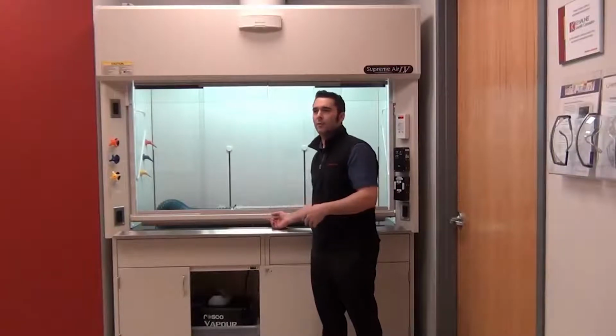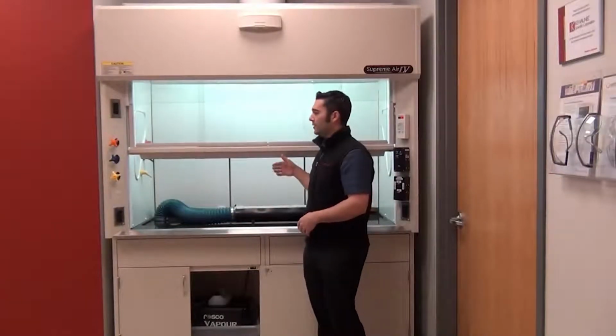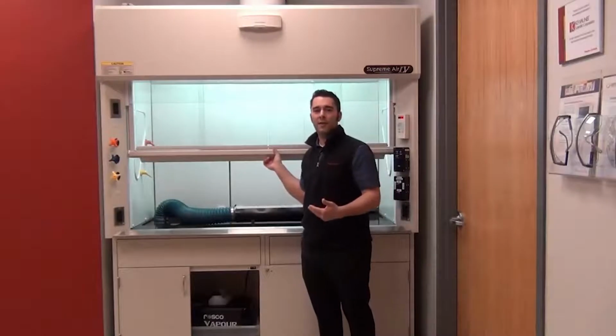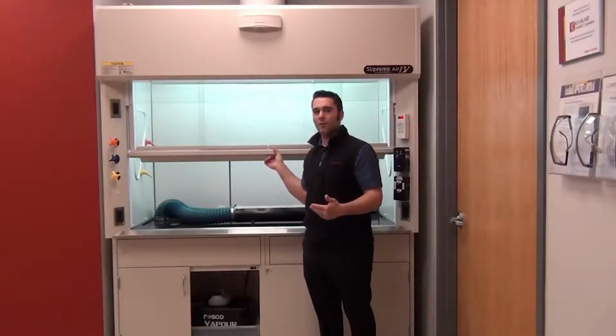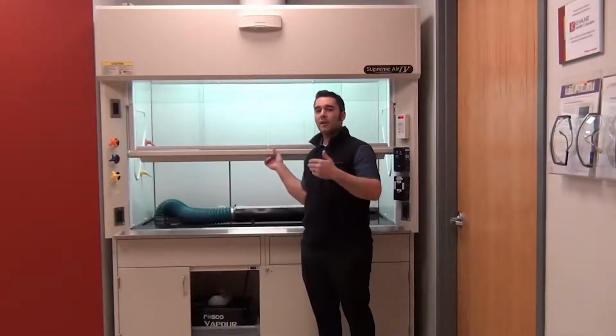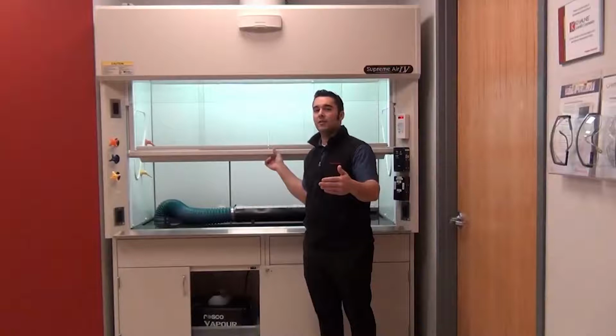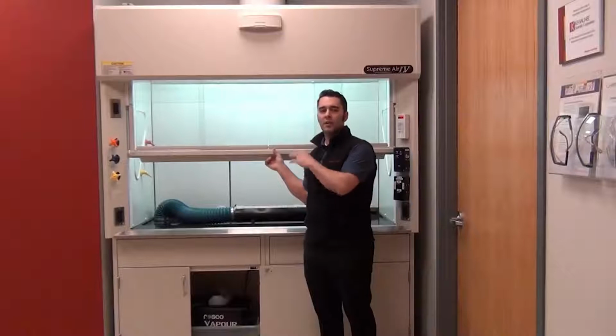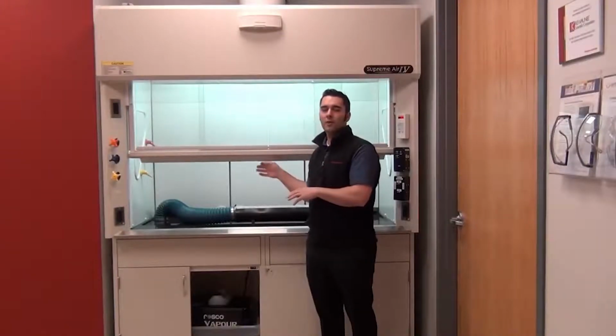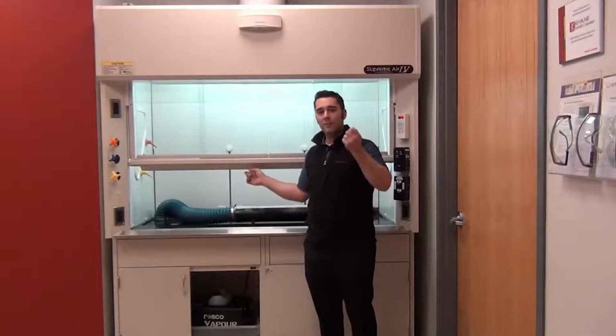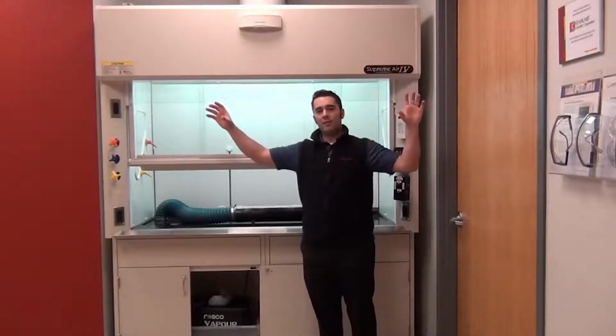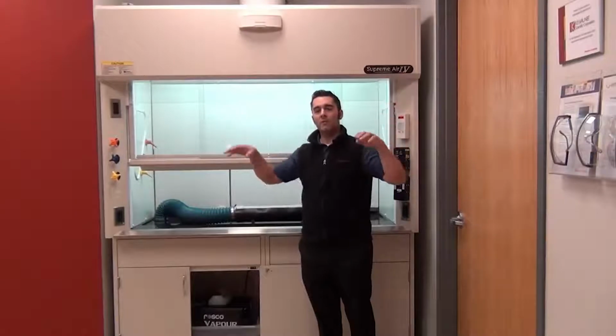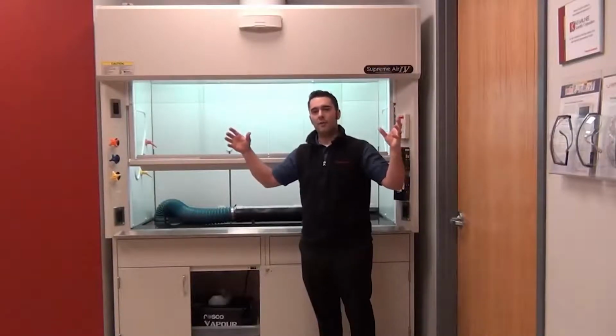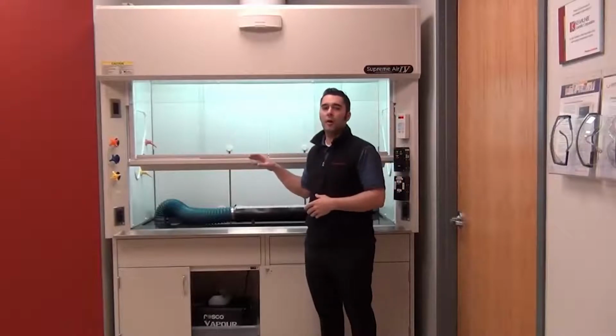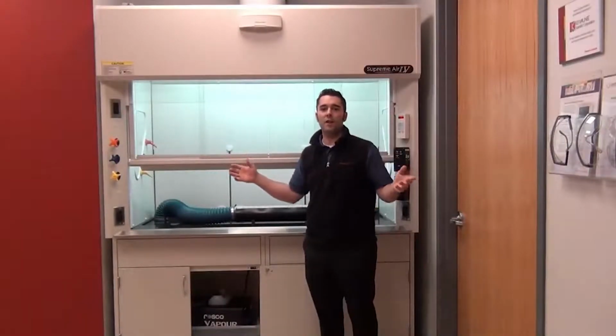and stable airflow control. The best thing about the Phoenix Controls Venturi valve is because they're pressure independent, I'm going to get very stable airflow control on top of the speed of response. So I can guarantee I have a 1 second speed of response to change in command. I can also guarantee that I have less than 1 second speed of response to changes in pressure that's going on inside the ductwork. So as I have other fume hoods in this lab and I'm moving them up and down, as the entire exhaust ductwork is all connected in a plenum, as one of those fume hoods moves, the entire pressure envelope in that ductwork is going to change, and it's going to require my fume hood valve to react to the pressure change in that whole scenario.